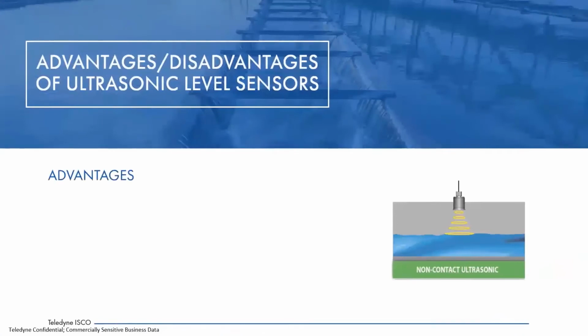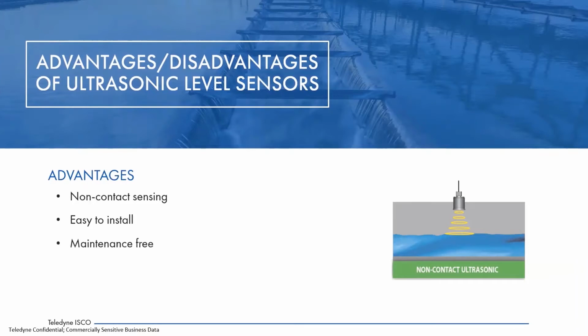Now, what are some of the advantages? They're non-contacting, so it's going to make them more maintenance free because you don't have to worry about debris or other things getting caught on the sensor. They're easier to install because you do not have to stop the flow to install your sensor. As I mentioned, they're maintenance free because they're out of your flow stream. But there are some disadvantages. You may be restricted on space, so you do have the deadband.